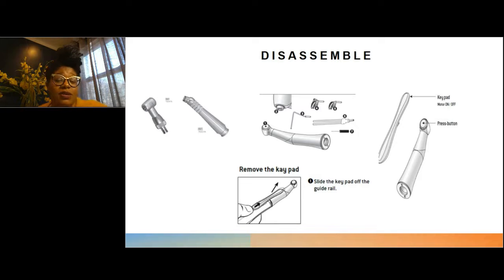So the next step we want to talk about is disassembling. Now, disassembling handpieces depends on the complexity of the handpiece. Here I've shown three different handpieces where, right inside of the IFU, it requires the handpiece to be disassembled. The first one here on the far left disassembles into three components. The one in the middle actually has cooling tubes, a Y manifold that should also be disassembled.